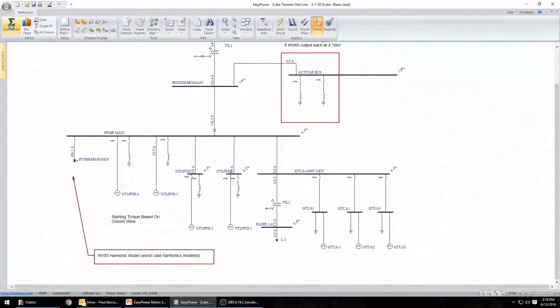And if we were to do a summation all, we'd say we were to simulate one of these soft starts starting. And like I said before, this is the worst case harmonic, so we actually have all of the harmonic currents associated with a soft start modeled at their maximum value. In reality, it will be less than this, but this is a starting point to determine where I might see problems. So in this situation, during the start, we might see 8.1% distortion. Likely will be less than that, but as a starting point, that's what I would be looking at.